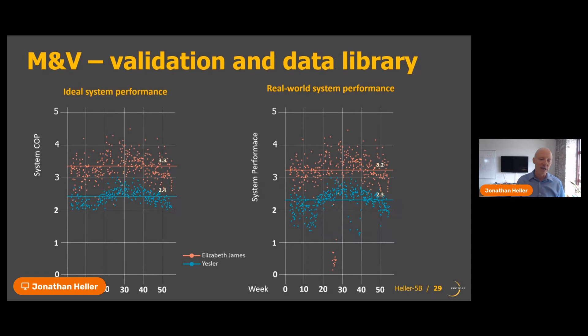We're using the EcoSim model, which we've developed using a very similar approach to what's used within the California Title 24 software for modeling these systems. Over the next few years, we want installations to submit annual performance data through a national database that PNNL is developing, so we can validate that the predicted system COP is actually delivered in the field—and if not, provide feedback to the manufacturer, to installer training, or to the modeling software to improve its predictive ability.